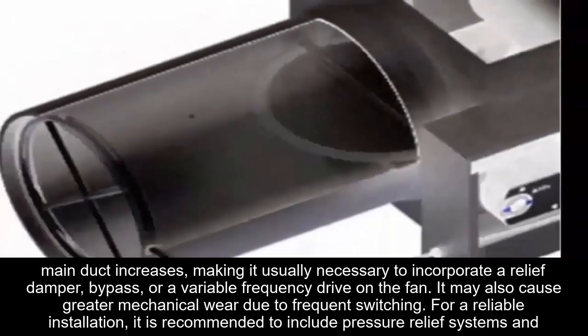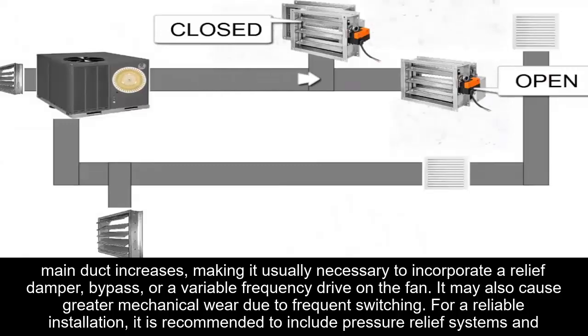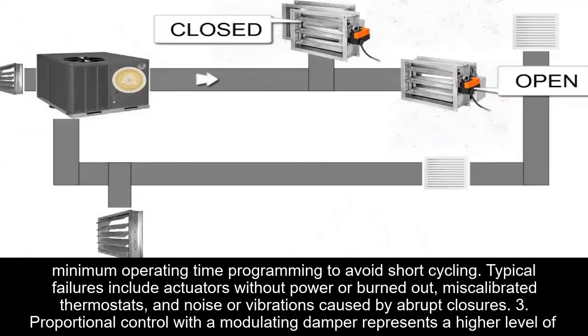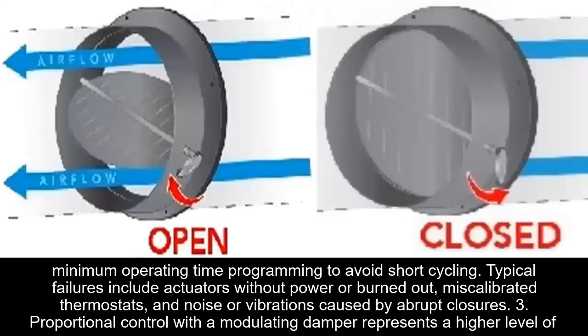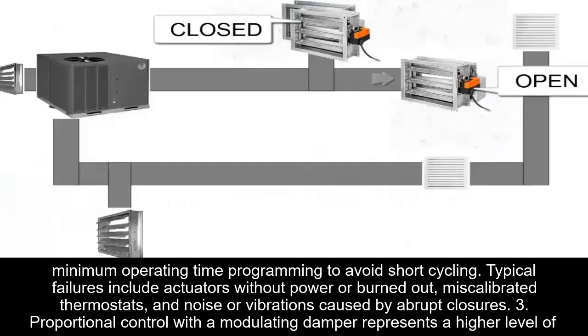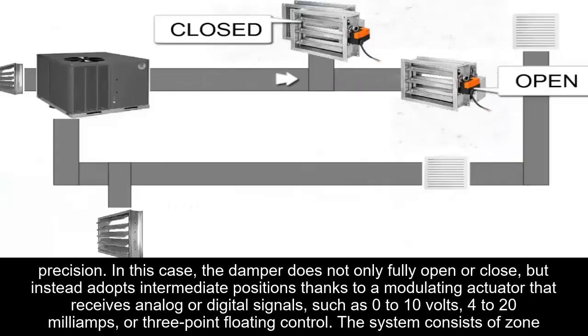For a reliable installation, it is recommended to include pressure relief systems and minimum operation time programming to avoid short cycling. Typical failures include actuators without power or burned out, miscalibrated thermostats, and noise or vibrations caused by abrupt closures. The third method corresponds to proportional control with a modulating damper.